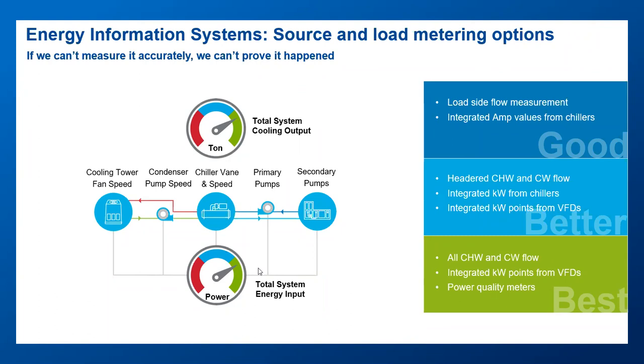The next level up, the 'better' level, is including accurate power readings for all the devices. Oftentimes, particularly when they're variable speed devices, you want that, and that kW point is often available from the variable speed drive.